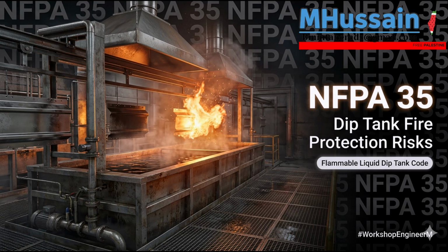Or spark. Right. The moment an operator walks down the stairs and flips on a standard, non-explosion-proof light switch, the resulting detonation would literally blow the foundation apart. That is terrifying. Because the risk of this invisible pooling is so high, the standard simply outlaws basements entirely. The primary floor must be at grade to allow heavy vapors to diffuse outward and to allow gravity drainage of spills. That makes the stakes incredibly clear.